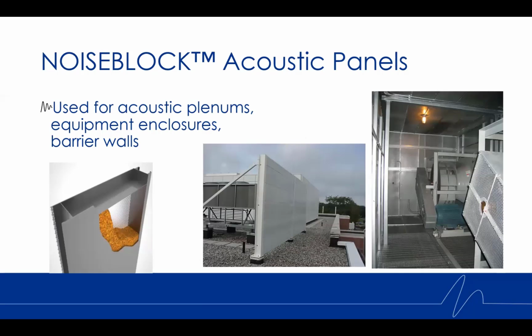Next, we have our noise block acoustic panels. This is a tongue and groove panel. Typically, it's 2 or 4 inches thick. And we will use these to make acoustic plenums. So you'll see these when you have a series of exhaust or outdoor air intakes on a building, typically in a mechanical room. Sometimes you'll see supply and return plenums as well. We will use them to create a barrier wall.